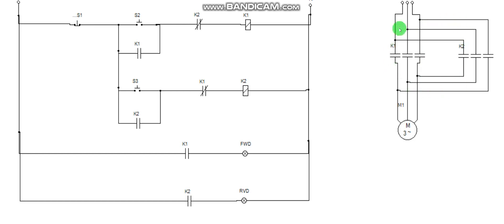Now, watch, just take a look at this. You see that this one goes the right sequence, but when you come to the opposite, this one supposed to be line 1, you go to line 3. Line 2 goes to line 2. This is line 3, you go to line 1. So you swap any two phases.